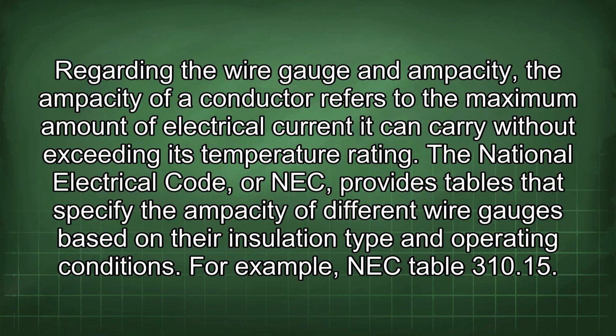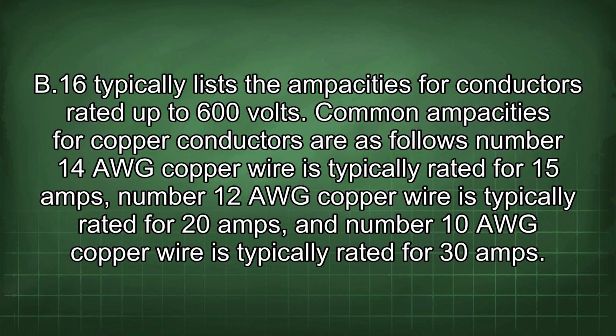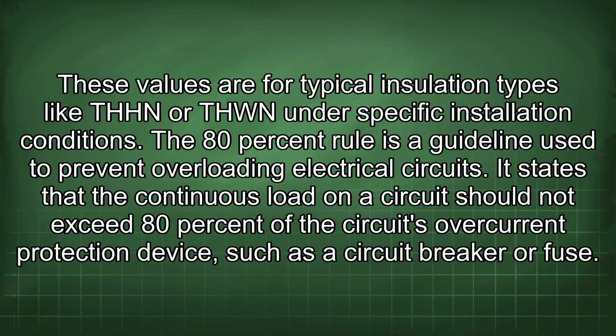Regarding the wire gauge and ampacity, the ampacity of a conductor refers to the maximum amount of electrical current it can carry without exceeding its temperature rating. The National Electrical Code, or NEC, provides tables that specify the ampacity of different wire gauges based on their insulation type and operating conditions. For example, NEC Table 310.15(B)(16) typically lists the ampacities for conductors rated up to 600 volts. Common ampacities for copper conductors are as follows. Number 14 AWG copper wire is typically rated for 15 amps. Number 12 AWG copper wire is typically rated for 20 amps, and number 10 AWG copper wire is typically rated for 30 amps. These values are for typical insulation types like THHN or THWN under specific installation conditions.